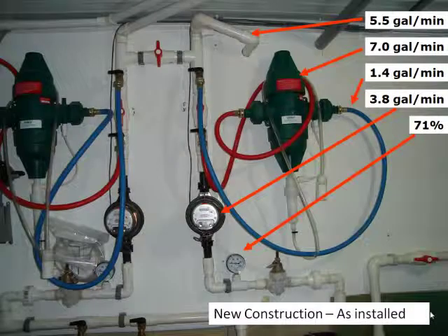Or this one. This is the best one I've got on this. This is a brand new barn in northwest Iowa. I was there about 10 days after pigs went in. So I was trying to figure out how much water they could really drink. So you're down to 20 PSI coming off a 3/4 inch line. Your water meter is a 5/8 inch meter. And by the way, that's your number one limit on water flow in a barn.